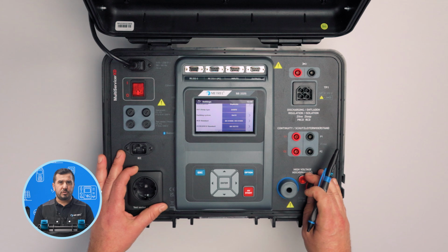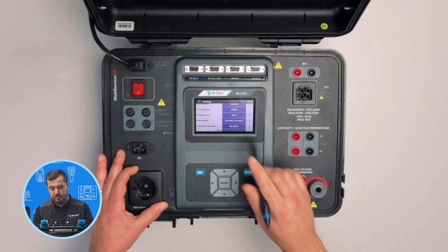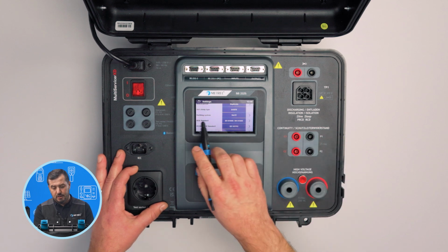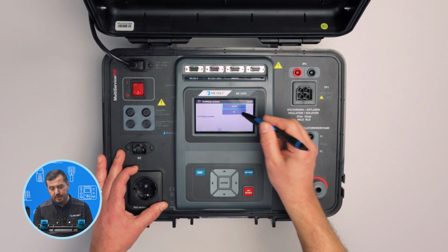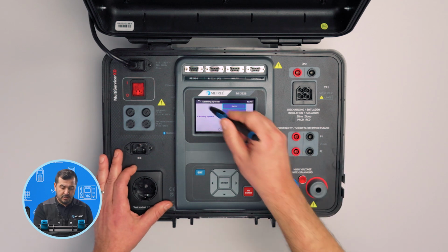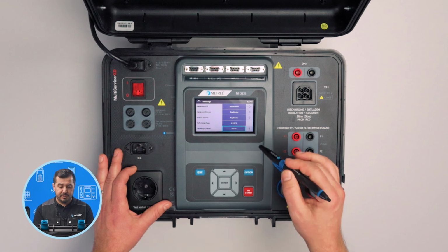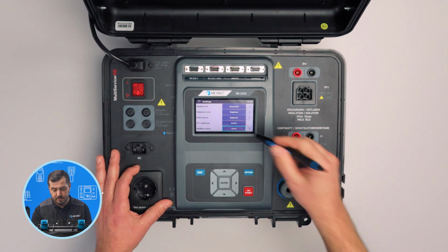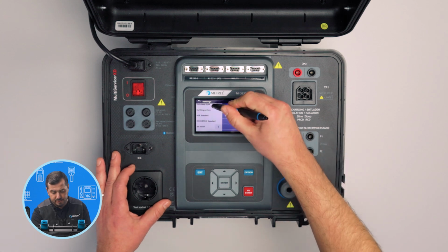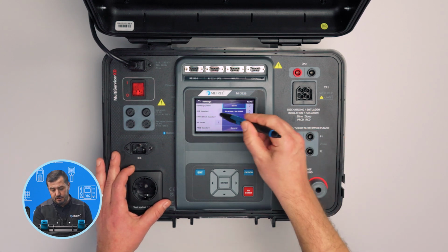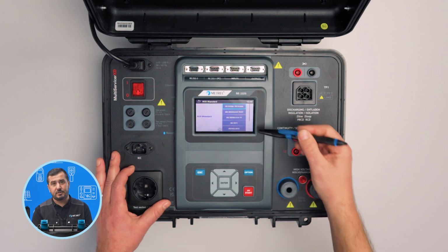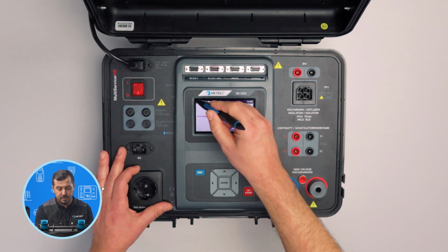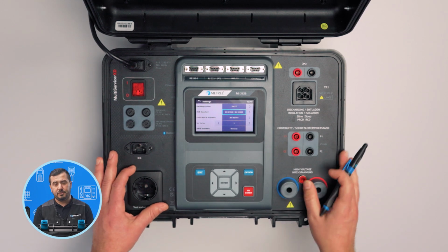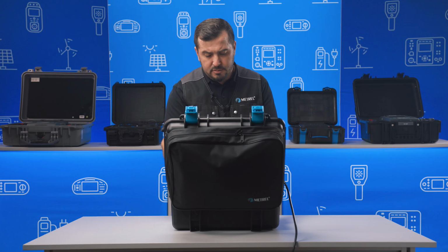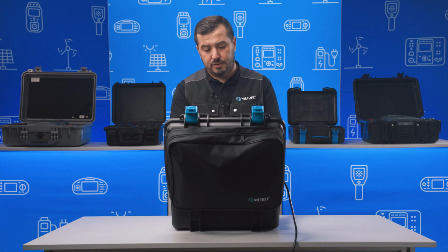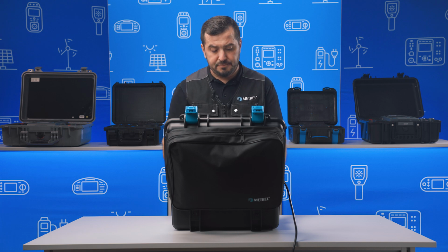This instrument currently supports only one optional clamp, so there is no option to change it. Earthing system, we can choose between TN, TT and IT earthing systems. Of course, this affects also some measurements. For detailed information, you will have to check the instruction manual. The same is with the selection of different RCD standards. So if I choose between different options, different limits will be applied to the measurements. The instrument also supports testing of EVRCDs and RCMs.